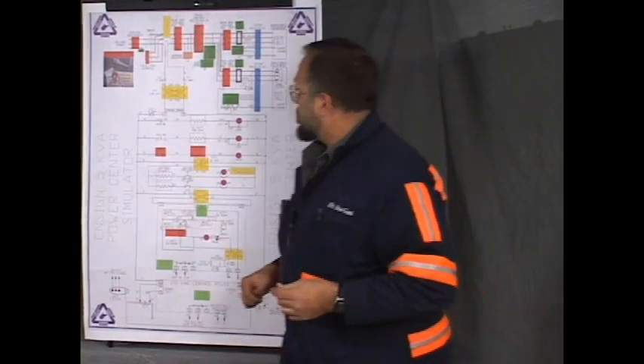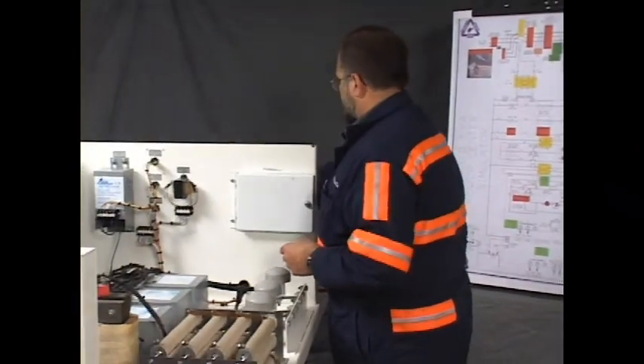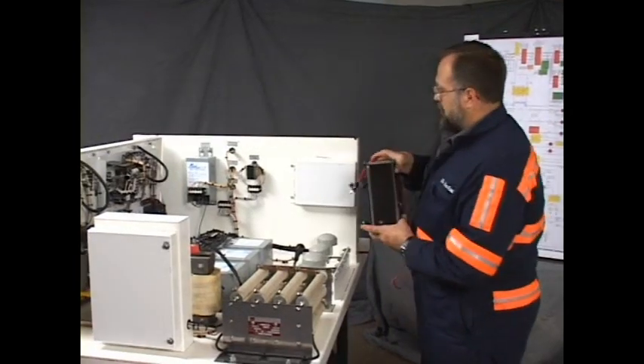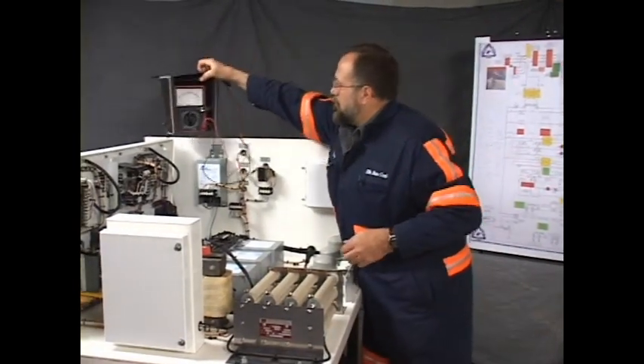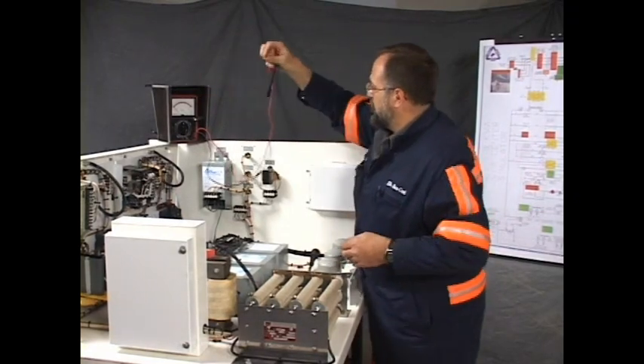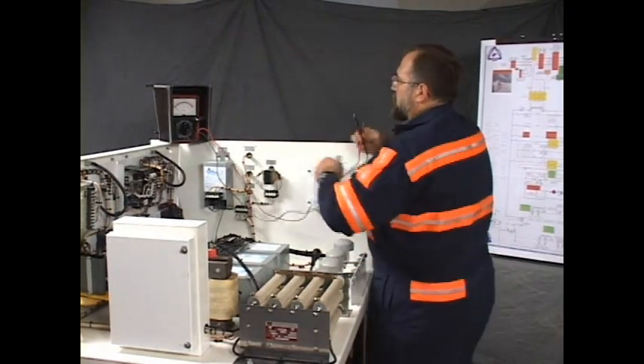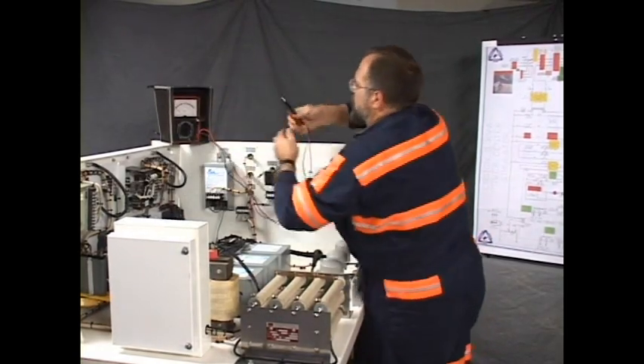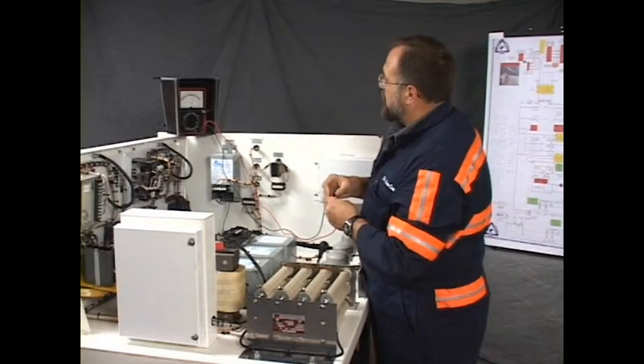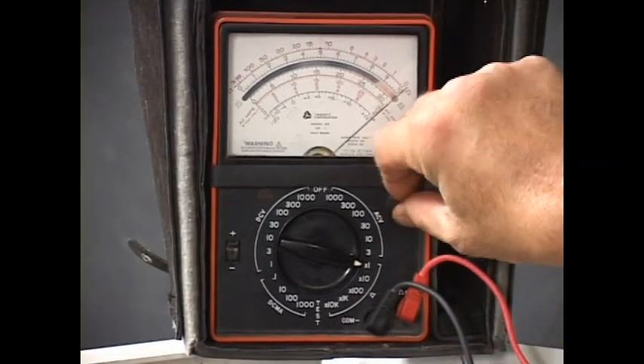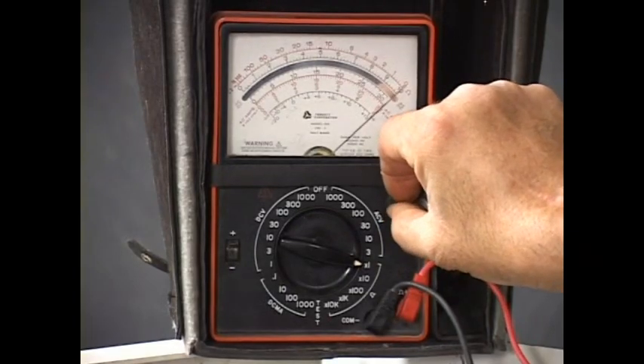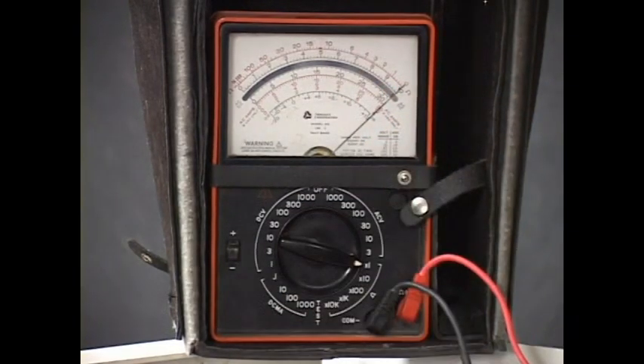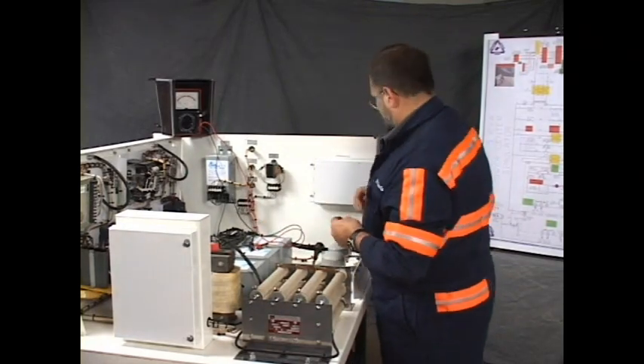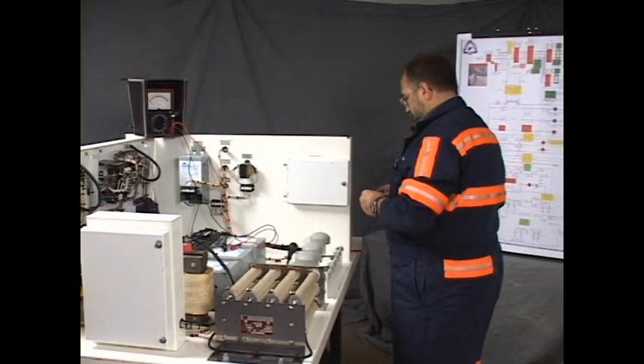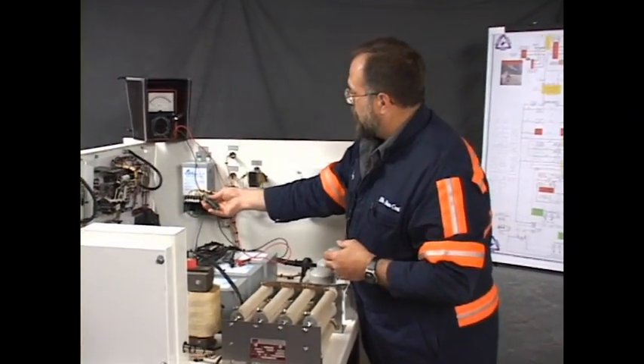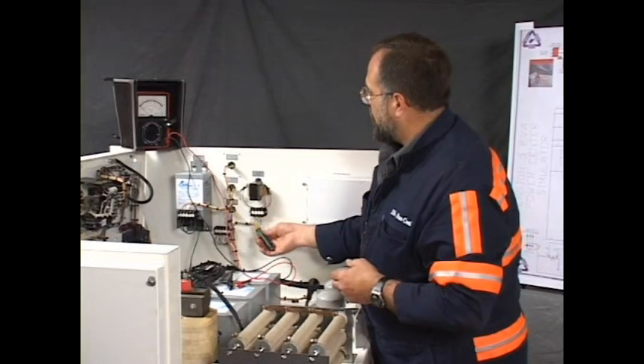Here we go. First thing that we're going to do is set our meter up where we can see it good. Turn the meter to the R times 1. Zero the instrument. And it always takes a tiny adjustment. Okay. Now our instrument is zeroed. I'm going to take a moment here to determine for certain that the power is off. And it is. There's no power on any of the incoming circuits.